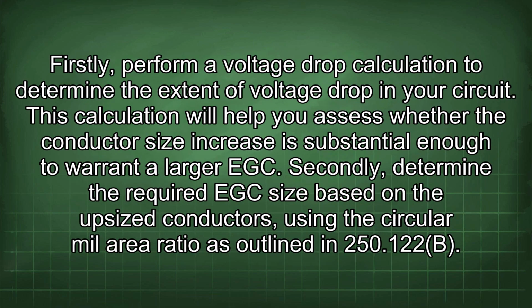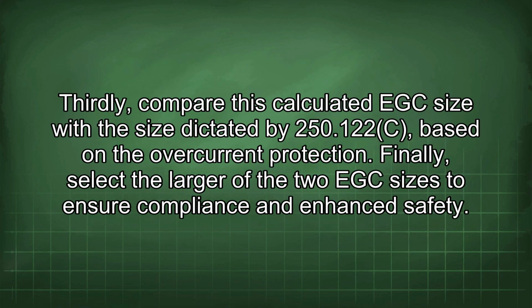Firstly, perform a voltage drop calculation to determine the extent of voltage drop in your circuit. This calculation will help you assess whether the conductor size increase is substantial enough to warrant a larger EGC. Secondly, determine the required EGC size based on the upsized conductors, using the circular mil area ratio as outlined in 250.122(B). Thirdly, compare this calculated EGC size with the size dictated by 250.122(C) based on the overcurrent protection. Finally, select the larger of the two EGC sizes to ensure compliance and enhance safety.